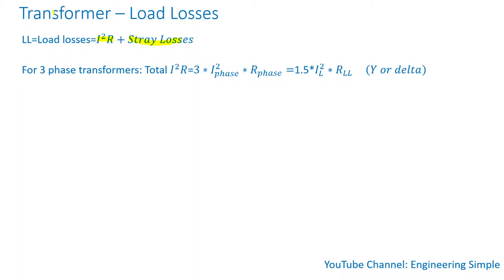For three-phase transformers, the total I squared R — since we have three phases — is three times the phase current squared times the phase resistance, or 1.5 times the line current squared times the line-to-line resistance. This is true for both Y and delta configurations.